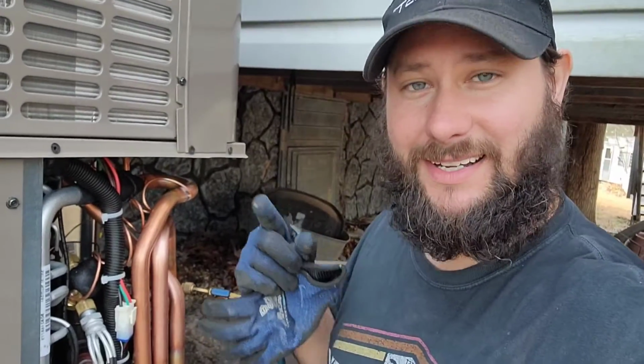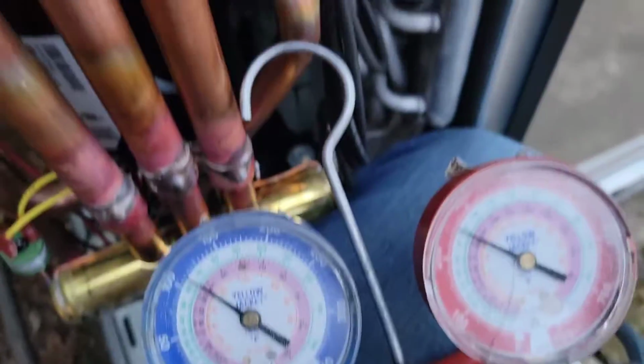Pressures look really good. I'm going to check the static pressure, check the airflow, the CFM, check the temperature split, and make sure that Glenna's unit is in good shape. The unit's working really well.